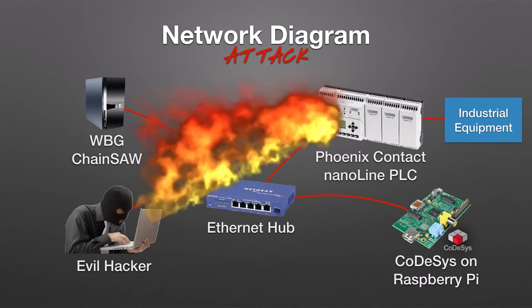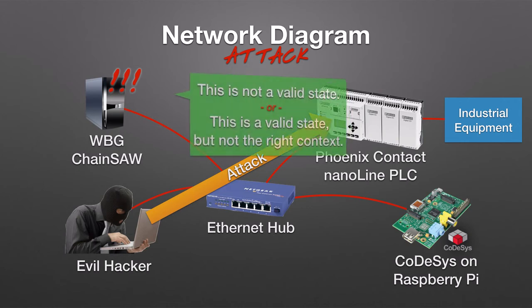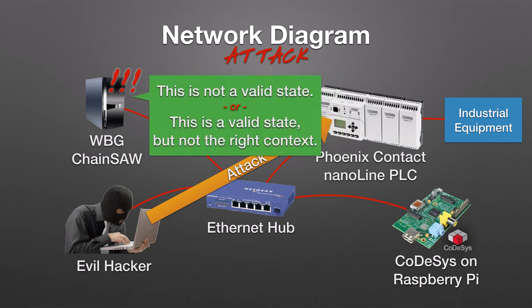To do that, he starts sending commands directly to the PLC, causing the pump to continuously run, the inlet valve to remain open, and the outlet valve to stay closed. As soon as the attack has any effect on the PLC's state, an alarm is raised, and one of two errors is reported: either the state caused is completely invalid, or a valid state is occurring in the wrong context.